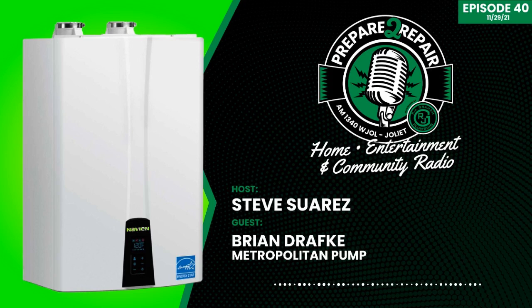So back to horsepower. When people go into a DIY store, not everybody is well versed on what sump pumps do, they just think the pumps pump water, and that's basically true. But if you grab a half horsepower or three-quarter horsepower pump for a small 18 by 30 inch pit, or 22 inch, code across the United States should really be a minimum of 24 by 30 because of the volume needed. If that pump does 100 gallons per minute, but your pit only holds about 15 to 17 gallons of water by the time it reaches the bottom, what do you need 100 gallons per minute for?